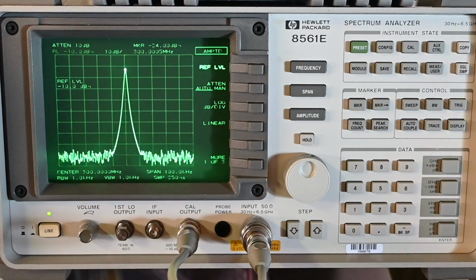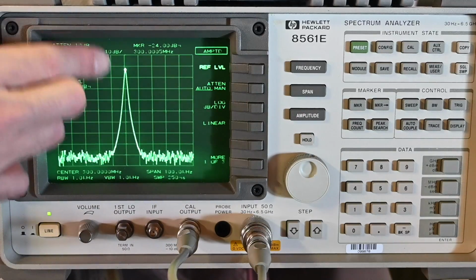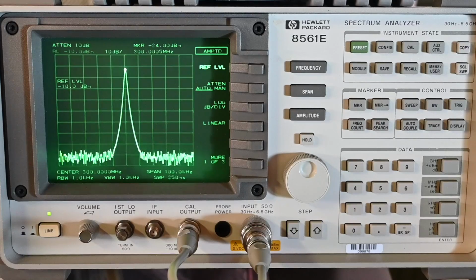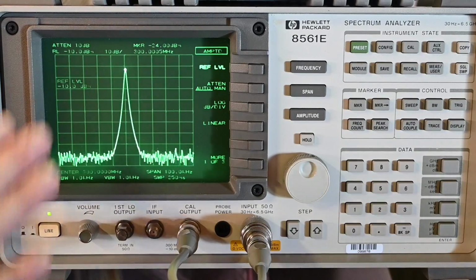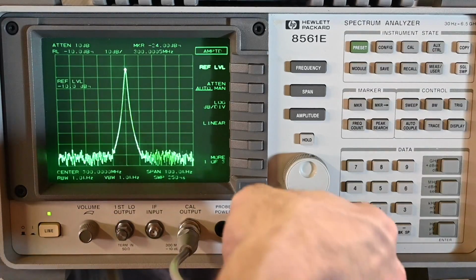And again, that calibration value is a very fine adjust, and it mentions in the service manual that it should be ideally pretty close to 0, or some value in there, but not skewed way off to the end, like 500 or something like that. And changing that value just is not bringing this into anywhere near the correct reading. But that's only one kind of issue that it's having with the inaccuracy on here. So let's take a look at something else.